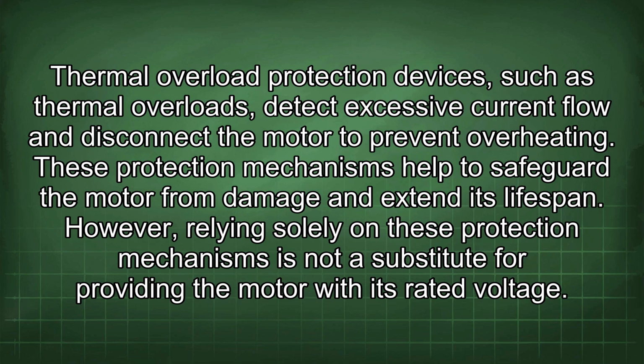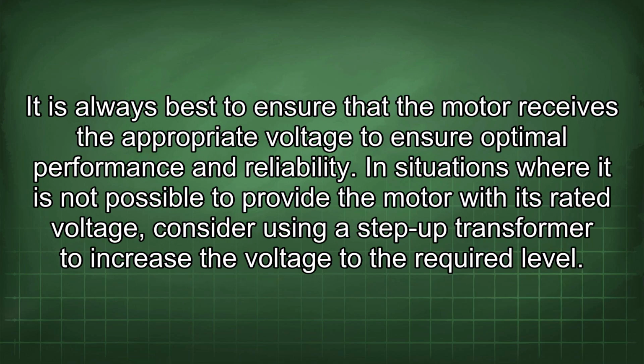Thermal overload protection devices, such as thermal overloads, detect excessive current flow and disconnect the motor to prevent overheating. These protection mechanisms help to safeguard the motor from damage and extend its lifespan. However, relying solely on these protection mechanisms is not a substitute for providing the motor with its rated voltage. It is always best to ensure that the motor receives the appropriate voltage to ensure optimal performance and reliability.